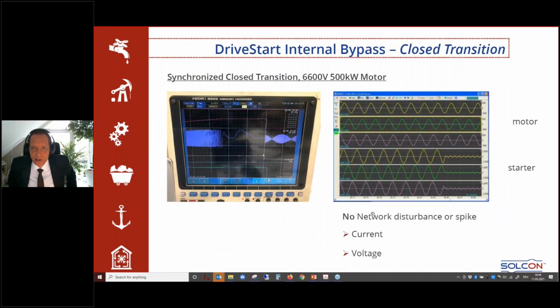Okay, what you can see here is the closed transition. On top, you see the motor current, and here you see the current with the inverter feeding. And from here on, you have the feeding via the network. That means when the bypass kicked in, the current of the inverter then goes to zero.